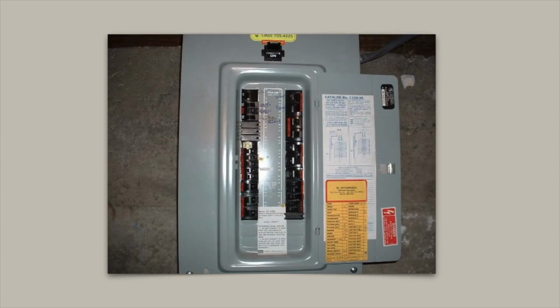Federal Pacific panels were shown not to meet the UL listing standards in the late 1980s. Since the UL label has been withdrawn, the panel should not be used as a residential panel. These breakers have a very high failure rate, and once they fail, the wiring will burn and thus cause a home fire. Smoke alarms have a lifespan of 8 to 10 years.